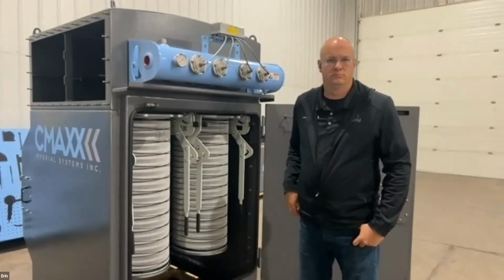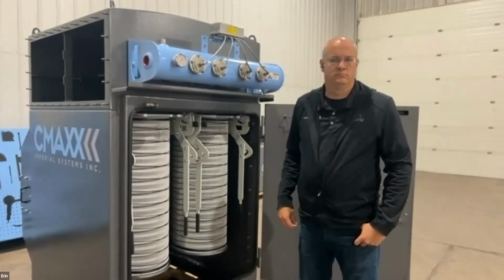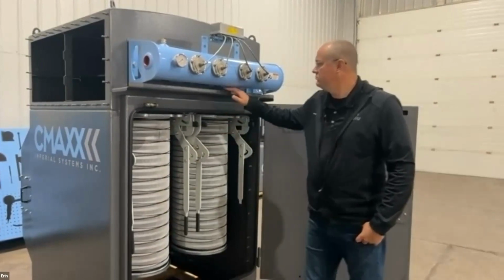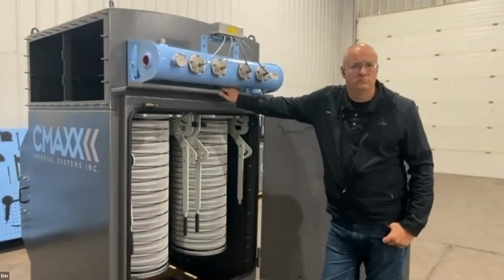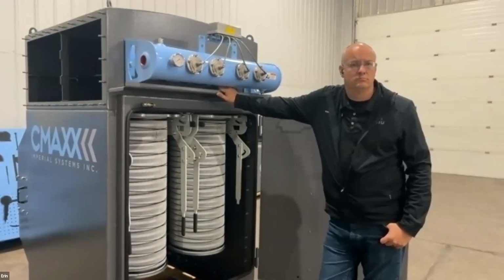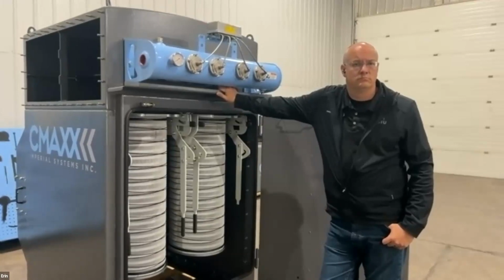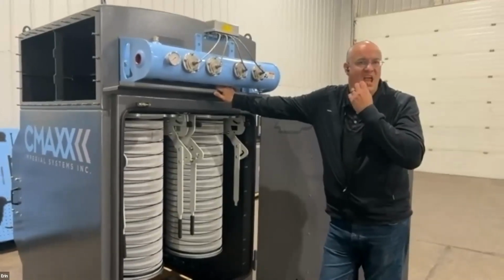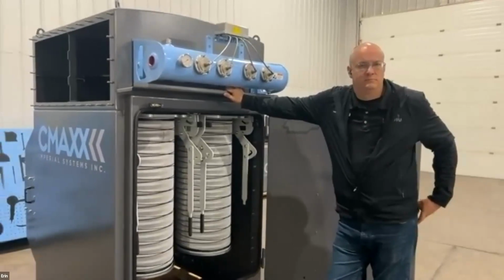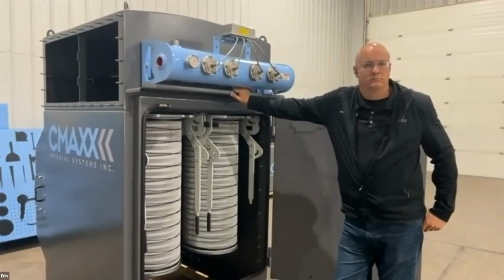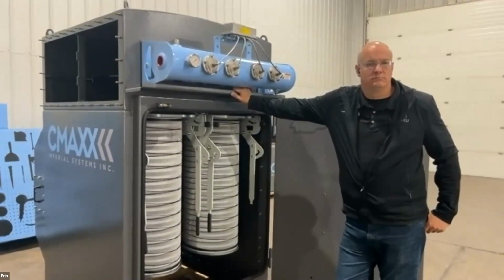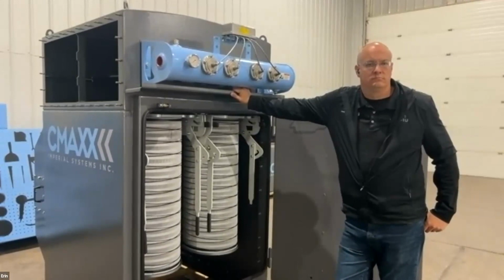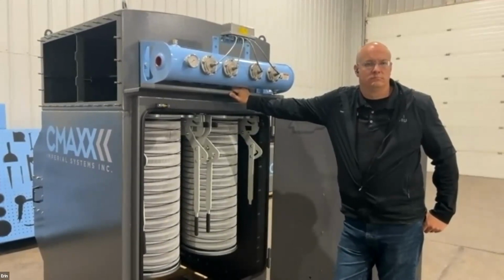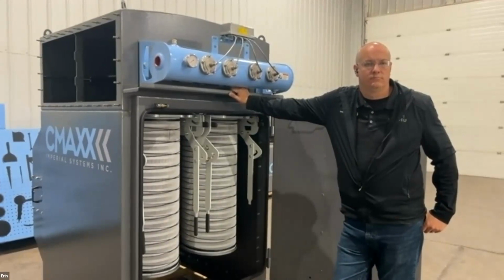Then you'd buy a little receiver dryer thing. There wasn't a lot of dough, but if you just add that to your shop air compressor with the separate line out, so you don't have to dry all your shop air. Yep, exactly. And most of the time, if you're a big industrial facility, you're gonna have a larger compressor or multiple compressors for standby. And you're gonna have a refrigerated dryer of some type, because all your machinery is gonna wanna be as dry as it can be.